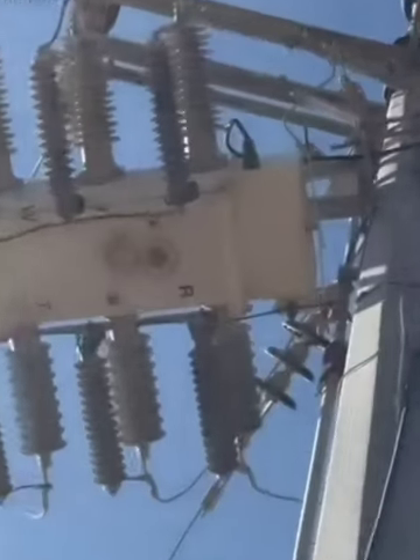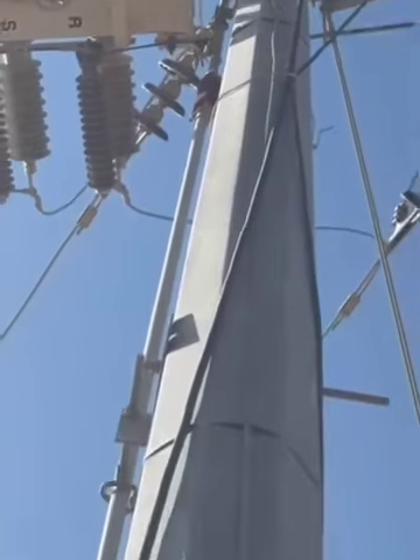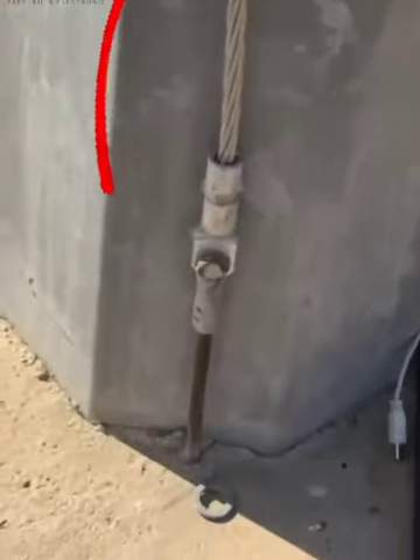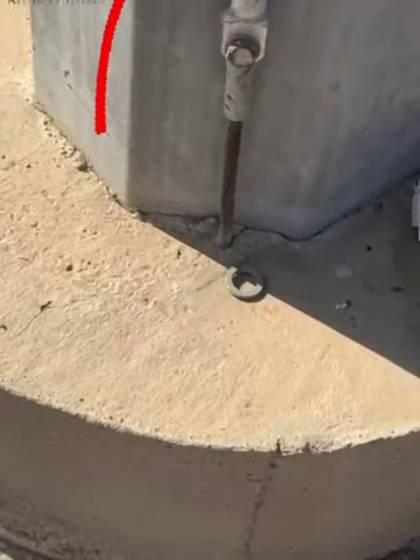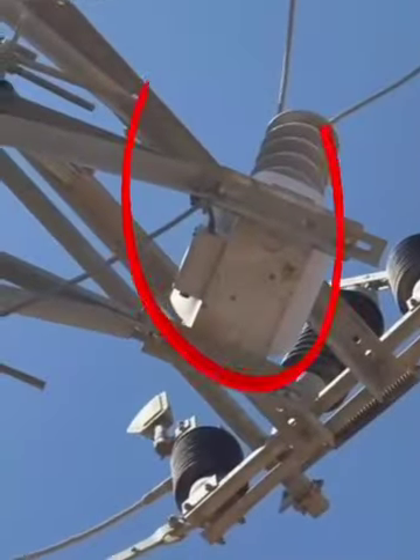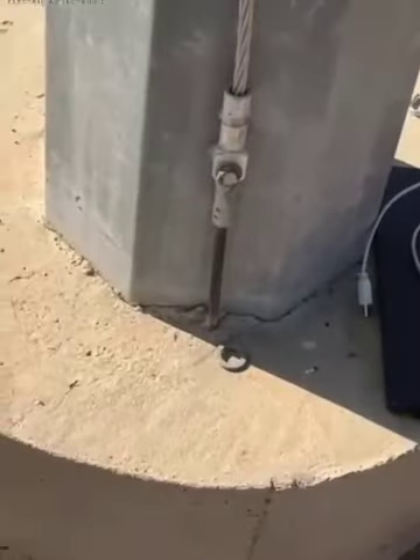After that, the earthing is very important. You have to first earth the tank and go down into the stake where it is actually earthed. And also you have to earth the VT, going down into the earth. And also, last of all, the controller has to be earthed, as you can see here.